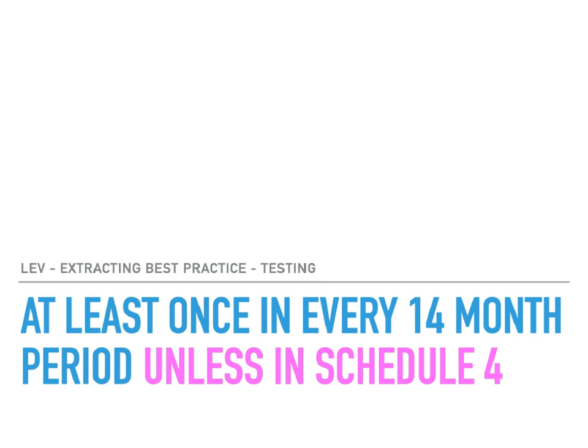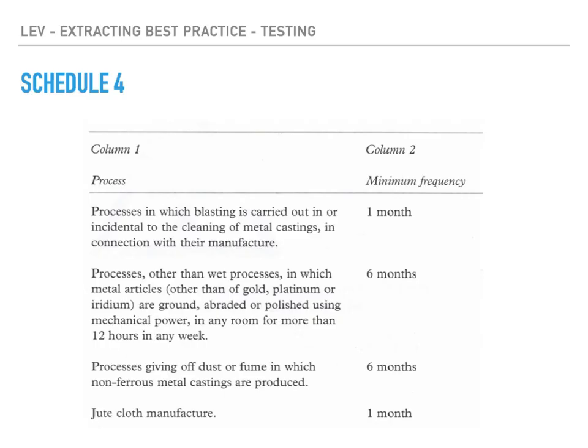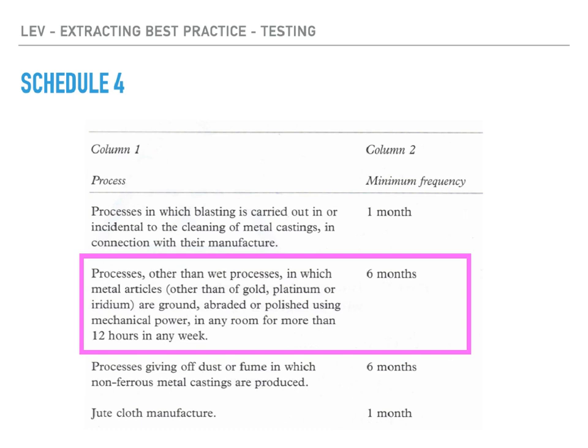So what is Schedule 4? This is Schedule 4, and most of these cases apply to foundries. However, if we look at this one here, it refers to the use of angle grinders or polishing where working metal components - and this is typically all fabrication shops. This is due to the abrasive nature of the dust being handled. They need to be checked more often, at least once every 6 months. But in our experience, this is hardly ever done.